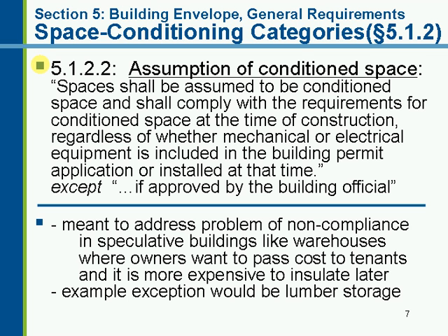The challenge here, what we've tried to do, is address this issue of non-compliance in speculative buildings. People have put up shell buildings like warehouses and said, well, I didn't put any equipment in it, so therefore it's not heated, it's not cooled, and whenever I find the tenant, they'll fit it out and take care of those costs. It's very problematic because it's difficult to track those through the construction process, and it's also much more expensive to insulate these structures later on after all the scaffolding's been removed. So the time to do the insulation is at the time of construction.